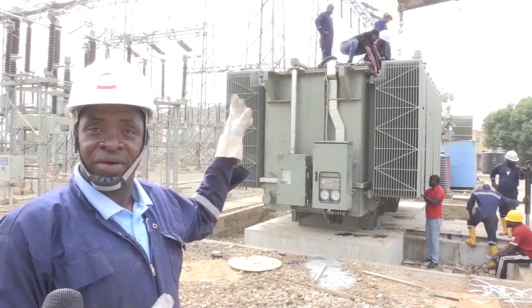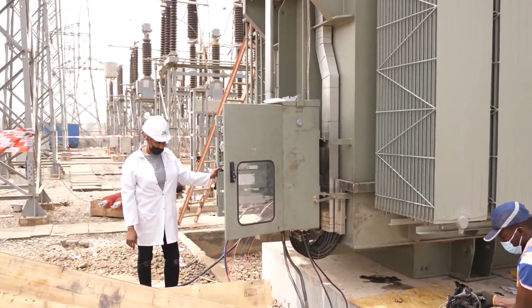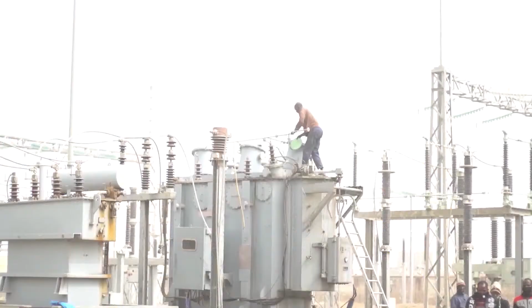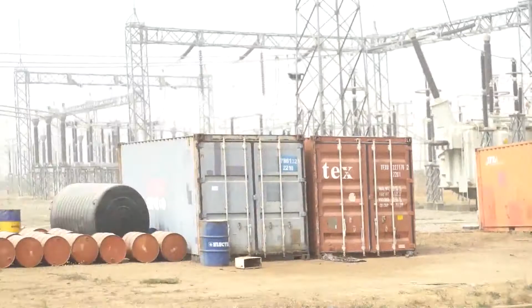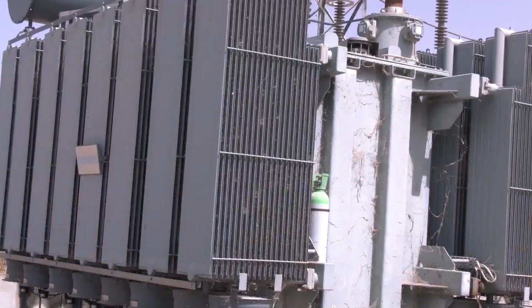TCN installed a 60 MVA power transformer at the 132 kilovolts Kubwa transmission substation in Abuja, and another 60 MVA transformer at the 330-132 kilovolts Kumbotso transmission substation in Kano. It then moved a 30 MVA mobile transformer, replaced by the new 60 MVA transformer in Kumbotso, to the new 132 kV Bichi transmission substation in Kano State to further increase bulk power available for distribution within Kano and its environs.